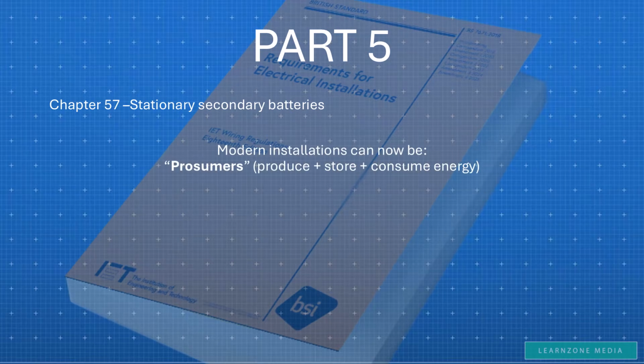As you know, modern installations are no longer just consumers. They are prosumers, they produce and store and consume energy. One example is stationary secondary batteries, which are now defined as a source of energy in Regulation 570.1. This creates new risks: backfeed from batteries, stored energy remaining after isolation, higher fault currents, and fire risks from lithium batteries. Chapter 57 exists to manage these new hazards properly.